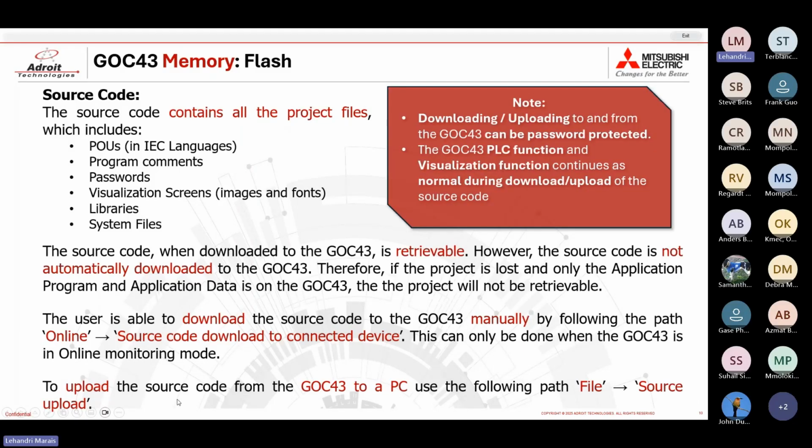Something to note when downloading or uploading to and from the GOC, you can password protect this action to protect your code. And this action also does not stop the normal operation of your GOC. While uploading or downloading your source code, the operation of these screens as well as the PLC logic continues as normal.